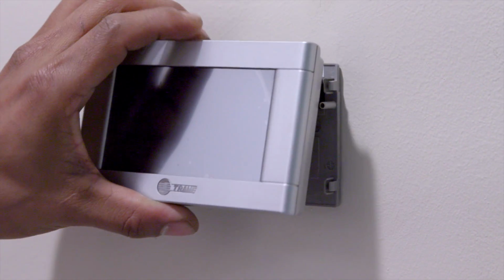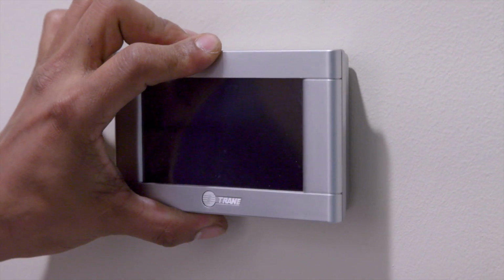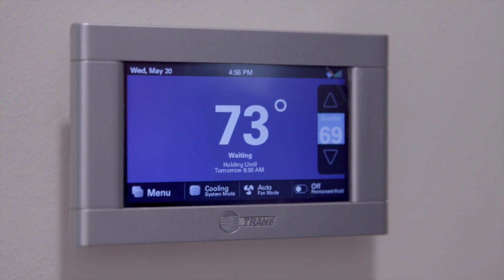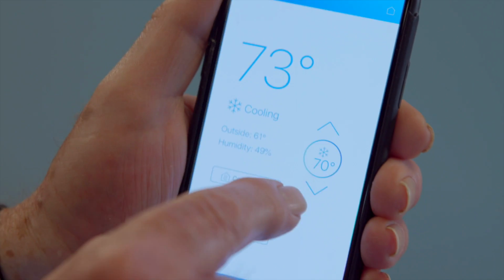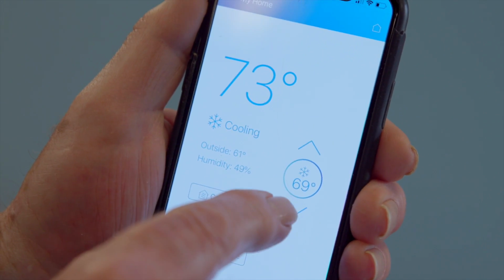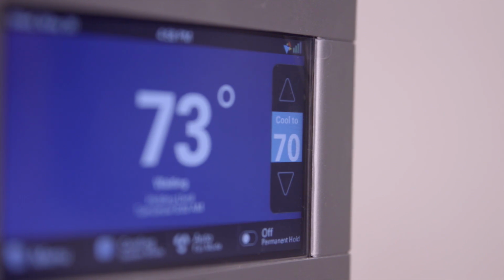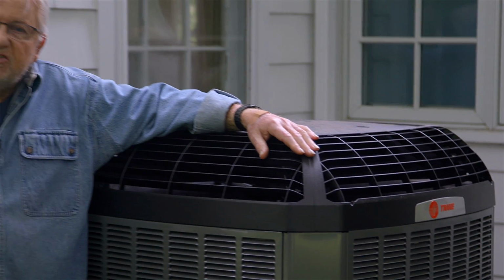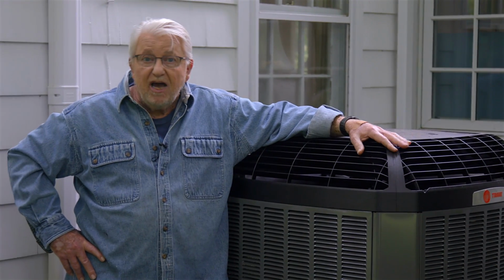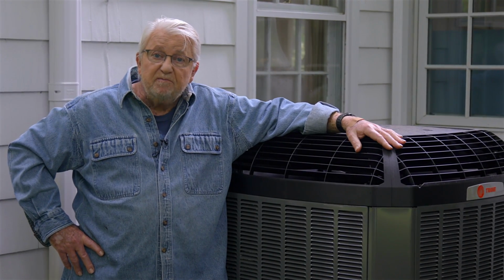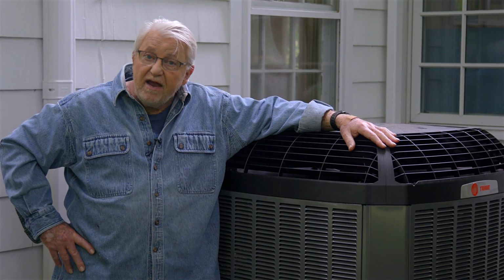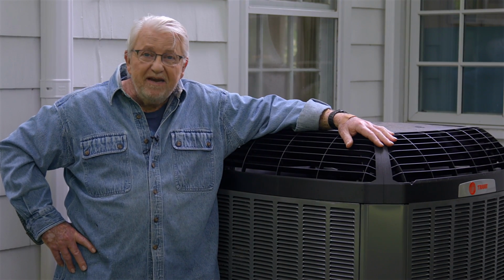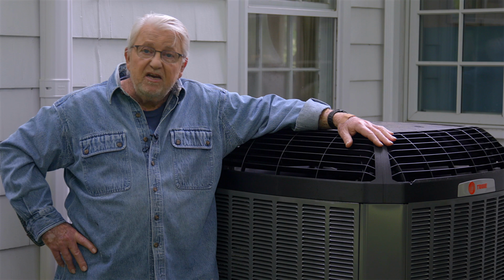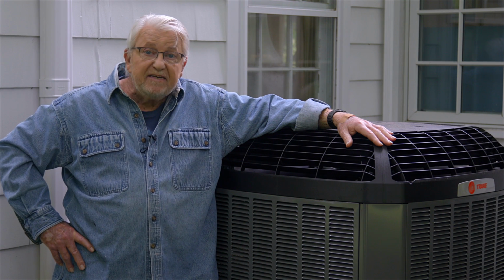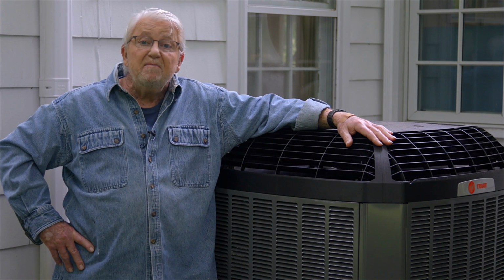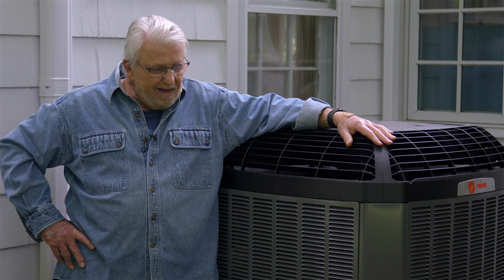The thermostat is the final piece in my new system. It's digital, programmable, and perhaps best of all, capable of being controlled from my smartphone. So there you have it, a complete central air conditioning replacement. Now, typically, a job like this takes 1 to 2 days. Now I have a system that's quieter, more economical to operate, able to filter and scrub the indoor air for pollutants, bacteria, and viruses, and can be operated from my smartphone. I'm good to go.